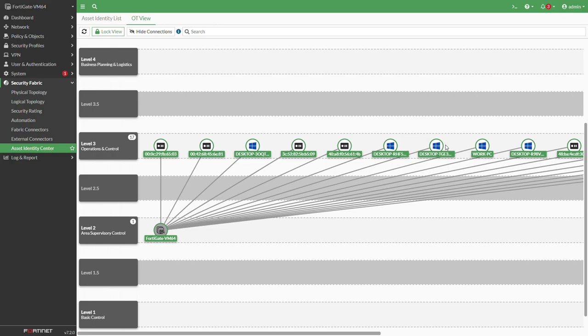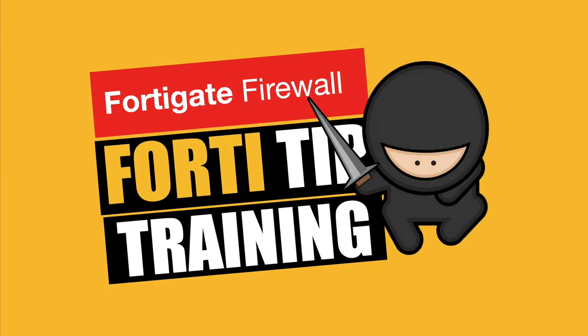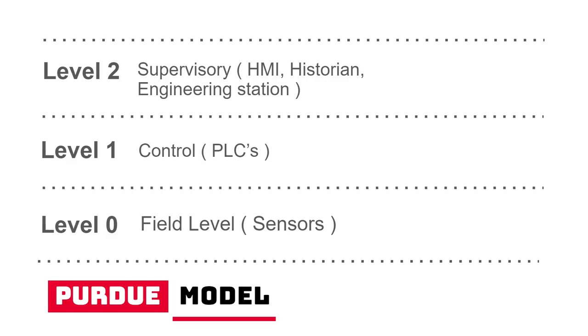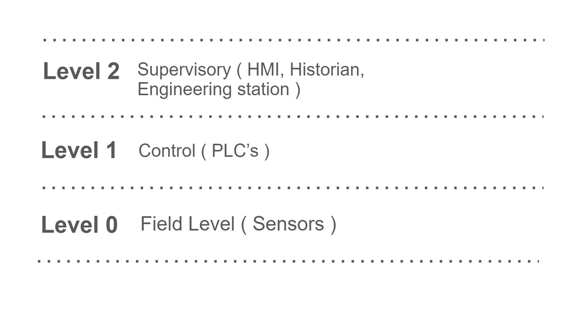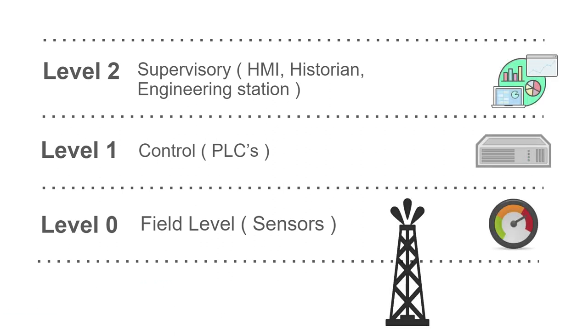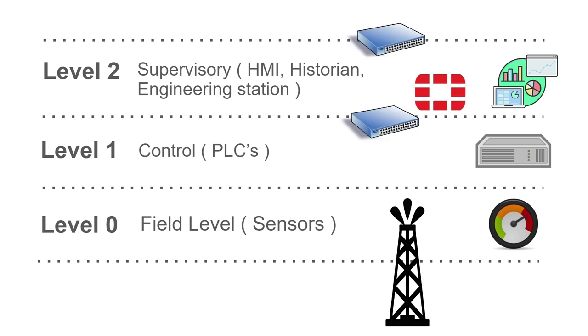In OT we have the Purdue model. It differentiates between the different levels, different control levels. The field level which is level 0 has all these sensors, and level 1 is the control level which has all the controls, the PLCs or RTUs. There's the supervisory level which has the historian, the HMI, the human machine interface that actually grabs all the information that the PLC gets from these sensors and delivers it to the HMI.